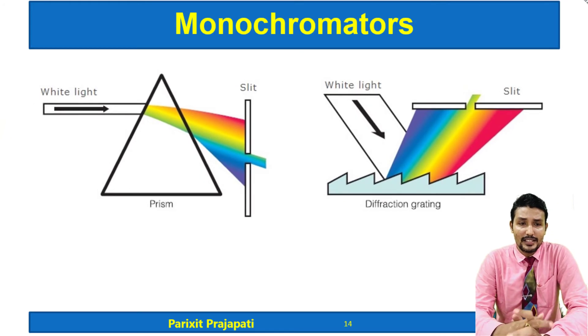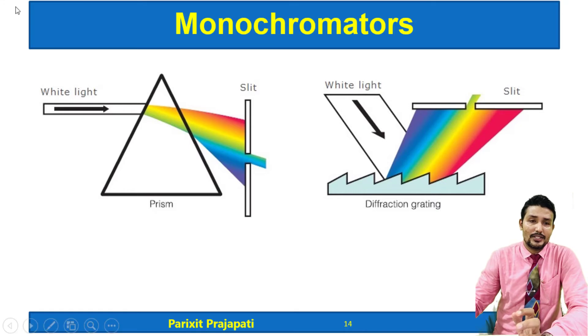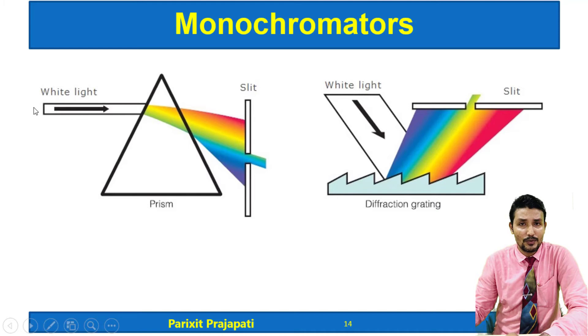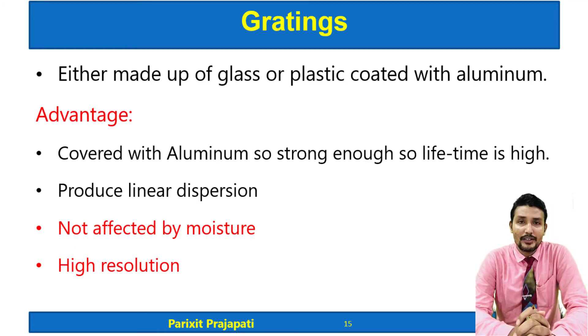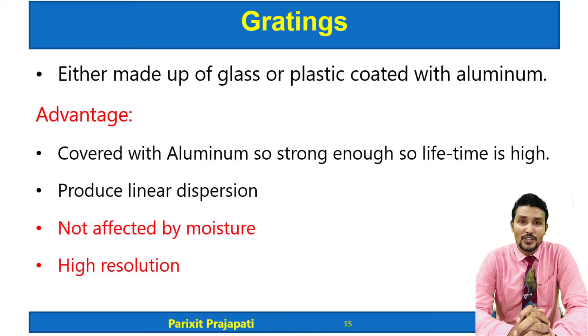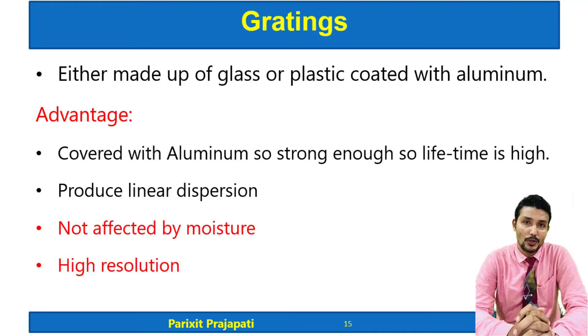Here is the diagram of prism and grating. A prism is familiar from UV-visible spectrophotometry. Gratings are based on diffraction or reflection, and have different grooves. The advantage of gratings is that they are made of glass or plastic coated with aluminum, giving them a high lifetime and greater strength. Gratings produce linear dispersion and have higher resolution than prisms. They are also not much affected by moisture.